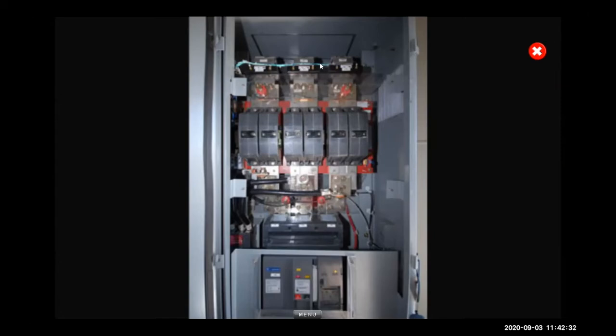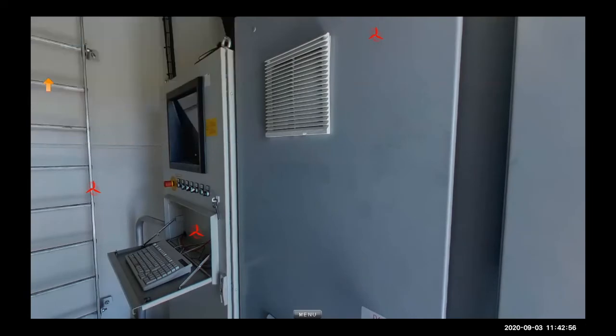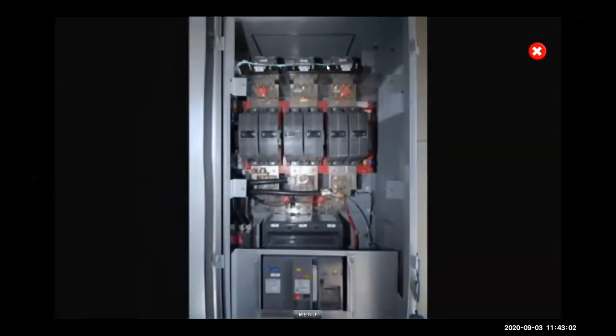You've got these wires that are connected up to that relay. So you're like, what are you talking about? We're going back into this box all the way over here. We talked about this MFR relay that's measuring the voltage on the turbine and the current through current transformers. That's them right there. So they're connected around the wires here on the top and on the bottom, and they're able to measure the voltage and send that signal out.